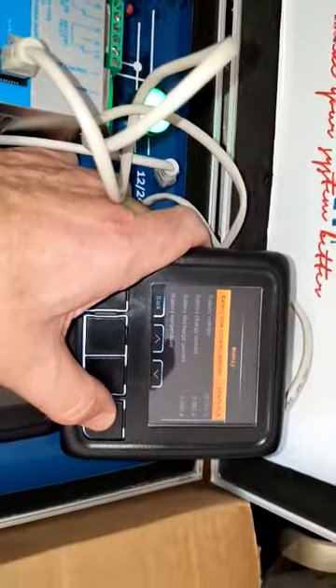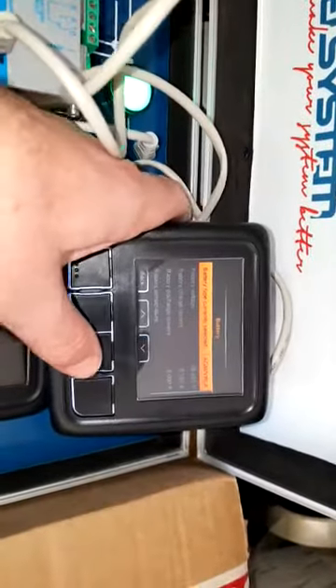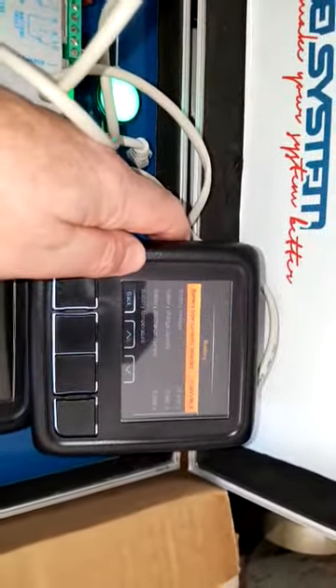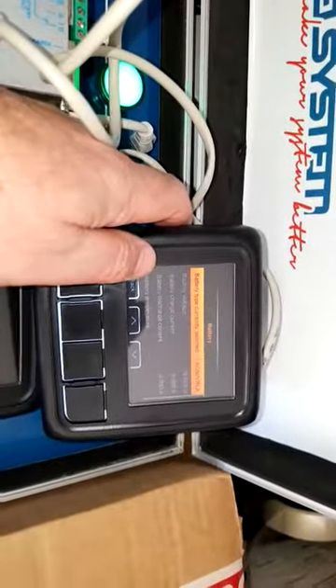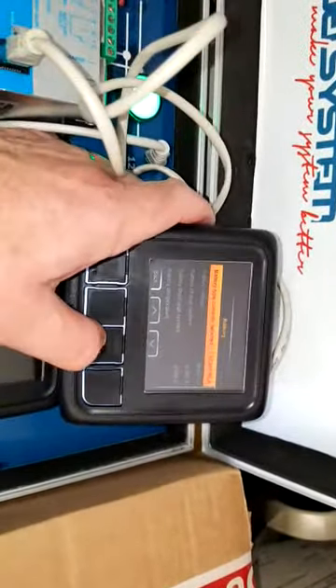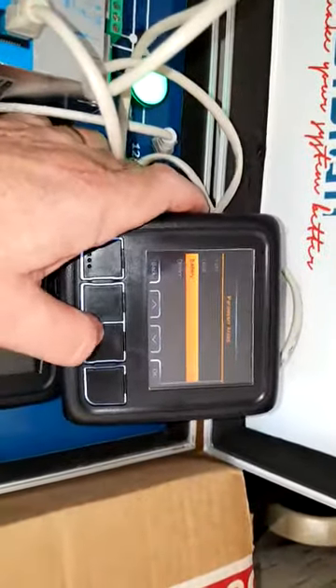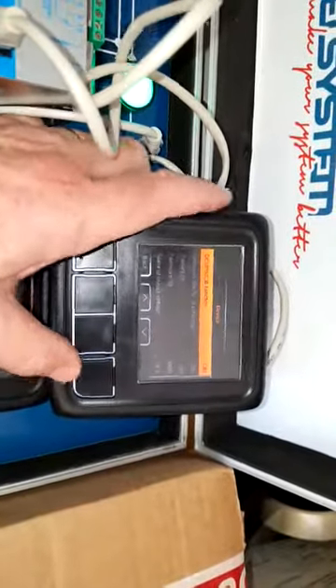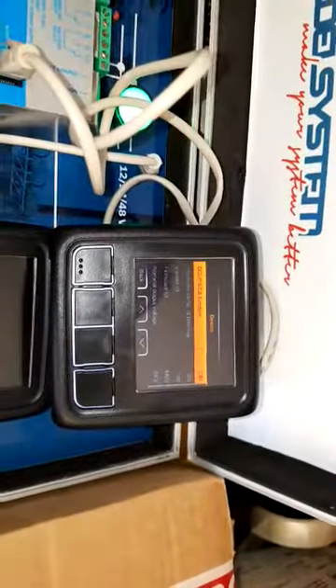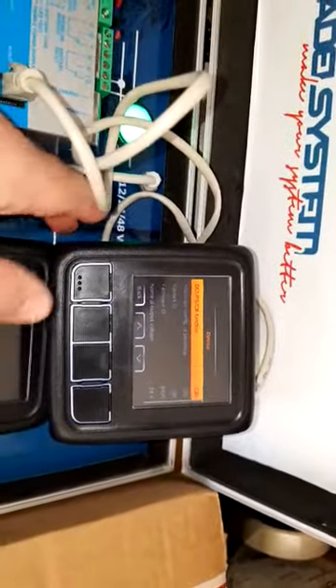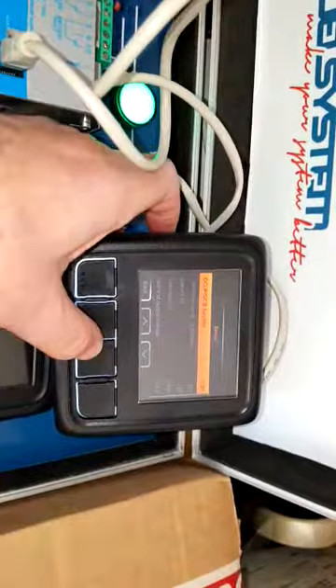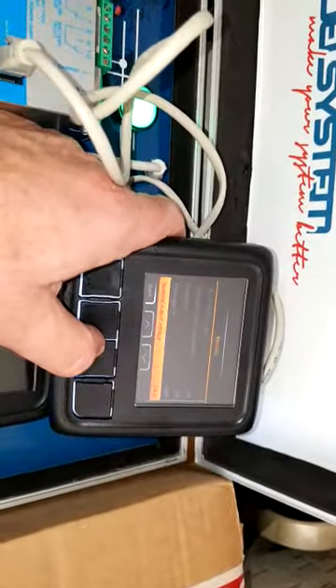Then you have the battery, and it'll tell you the battery type. This one is sealed lead acid, battery voltage, battery charge current, battery discharge current, and the battery temperature. There's no temperature probe attached, therefore it doesn't tell me that. And then you have the device, so it'll tell you what type of device it is. It'll tell you the hardware configuration, the variant ID, firmware ID, and normal voltage output as set.